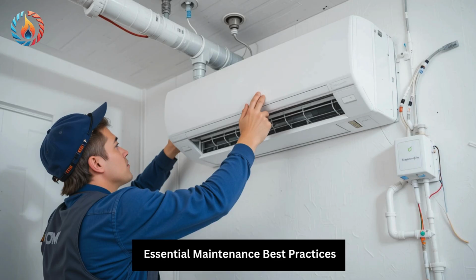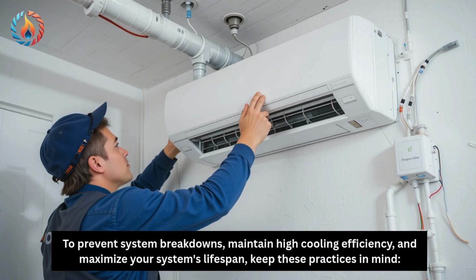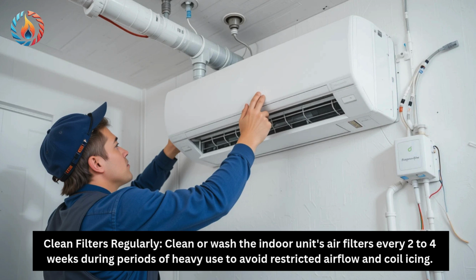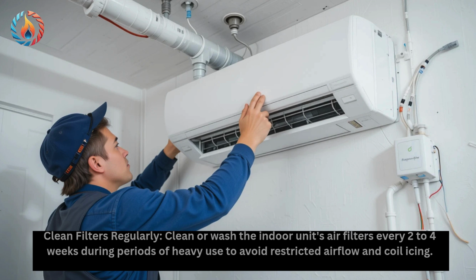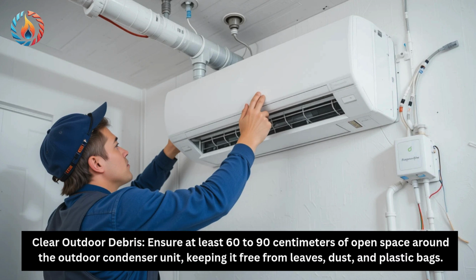Essential maintenance best practices. To prevent system breakdowns, maintain high cooling efficiency, and maximize your system's lifespan, keep these practices in mind. First, clean filters regularly. Clean or wash the indoor unit's air filters every 2 to 4 weeks during periods of heavy use to avoid restricted airflow and coil icing. Second, clear outdoor debris. Ensure at least 60 to 90 centimeters of open space around the outdoor condenser unit, keeping it free from leaves, dust, and plastic bags.